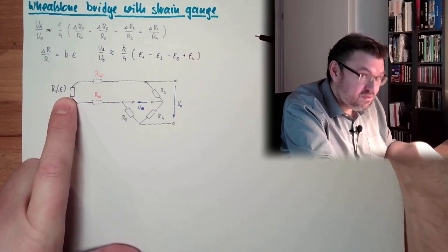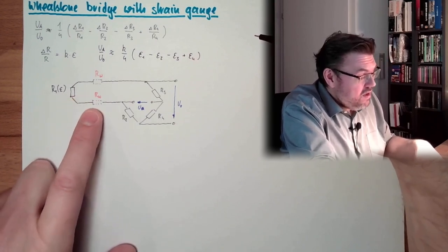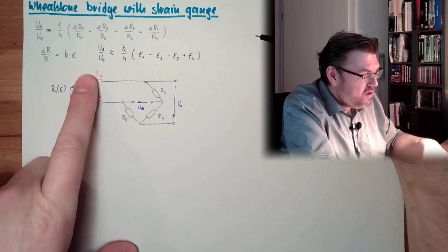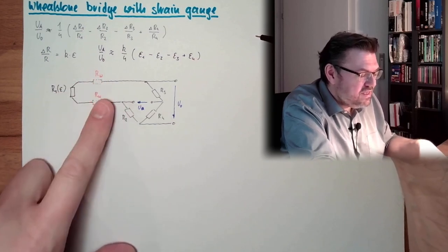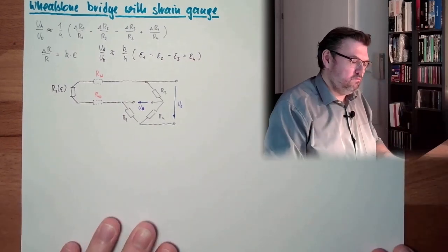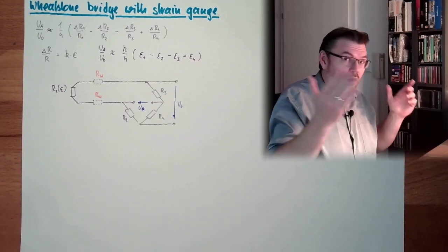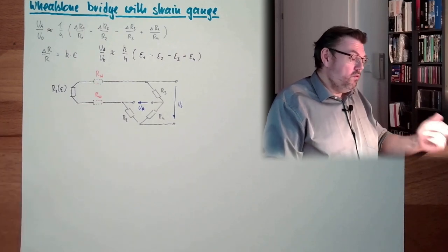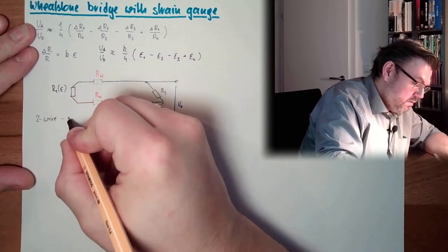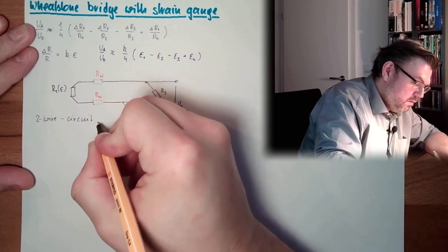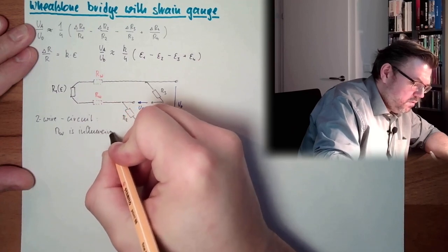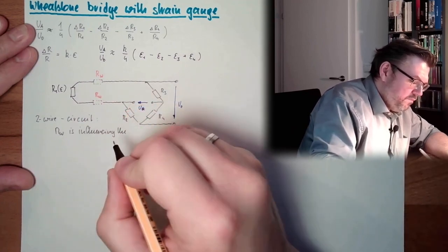So I'm measuring apparent strain even if there is no strain and no force — just because of those wire resistances, which cause a virtual delta R1. This is called the two-wire circuit, where Rw is influencing the measured value.